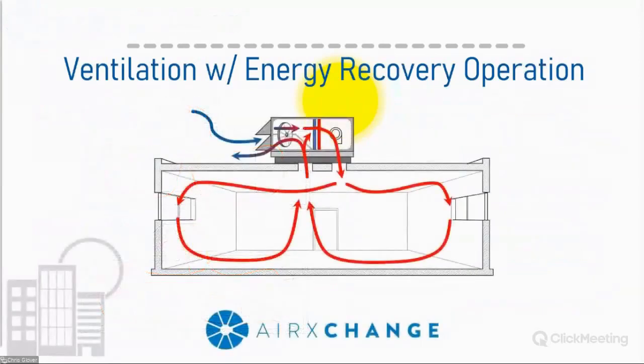So you can see that the air still comes into the unit, but instead of the heating and cooling coil treating the air, you're now shifting it over to the energy recovery component. The energy recovery is going to recover and precondition the air and deliver it into the space for dilution purposes.